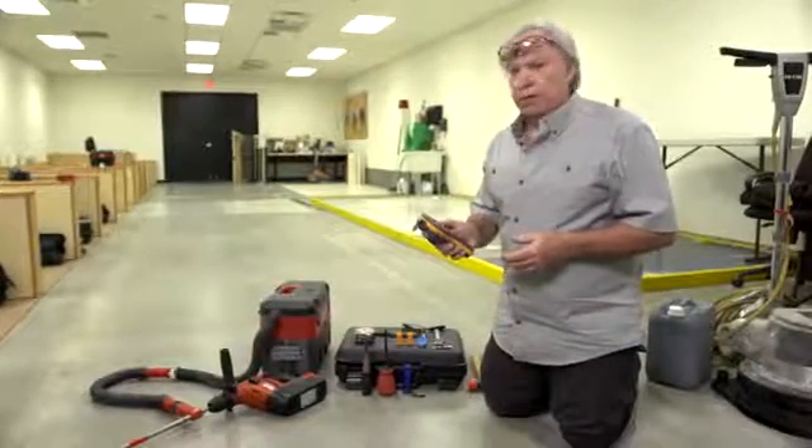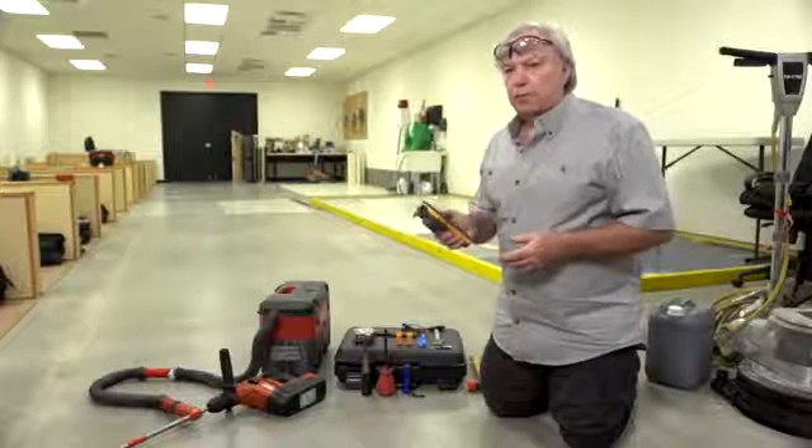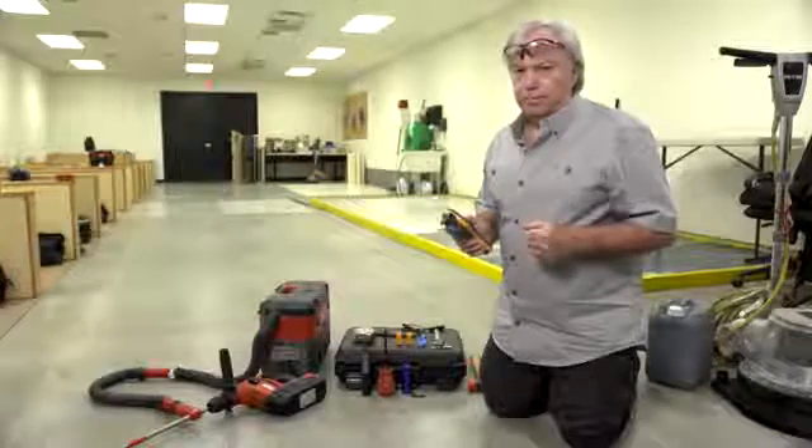Okay, let's get on with the demonstration. We're now going to demonstrate the use of the Protimeter MMS2 unit to measure the concrete internal relative humidity according to ASTM F2170. This standard determines the relative humidity at specific target depths.